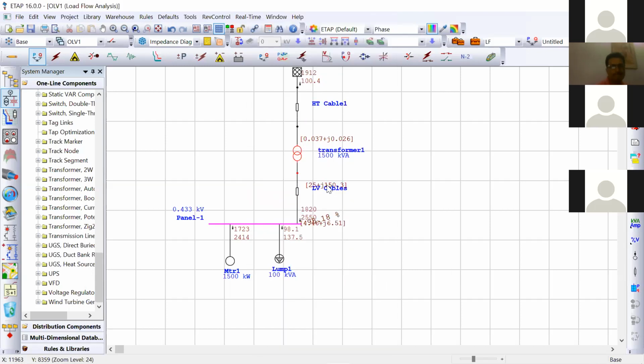So earlier this was something different. Now it has got some different values. So losses are increased because of heavy loading conditions. And there is a flow of reactive power from the source. That means it is consuming more reactive power from the source. That means power factor is getting reduced. So now I can decide whether I need to put a capacitor over here or not.